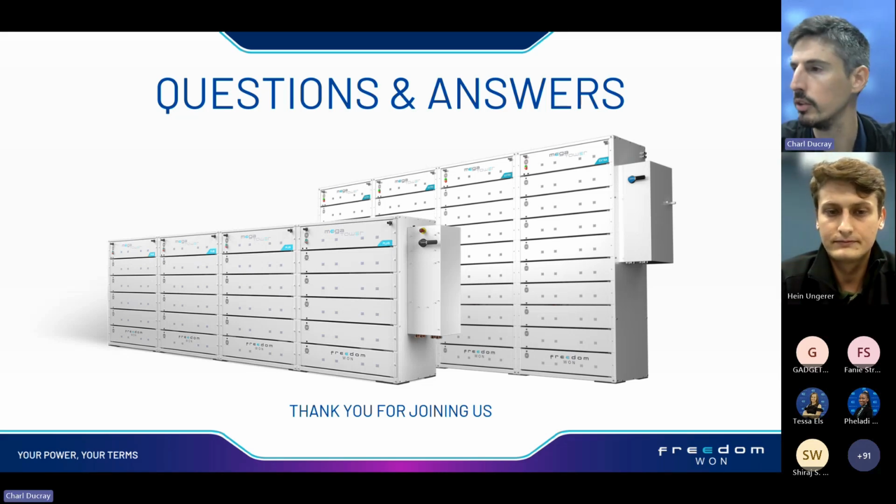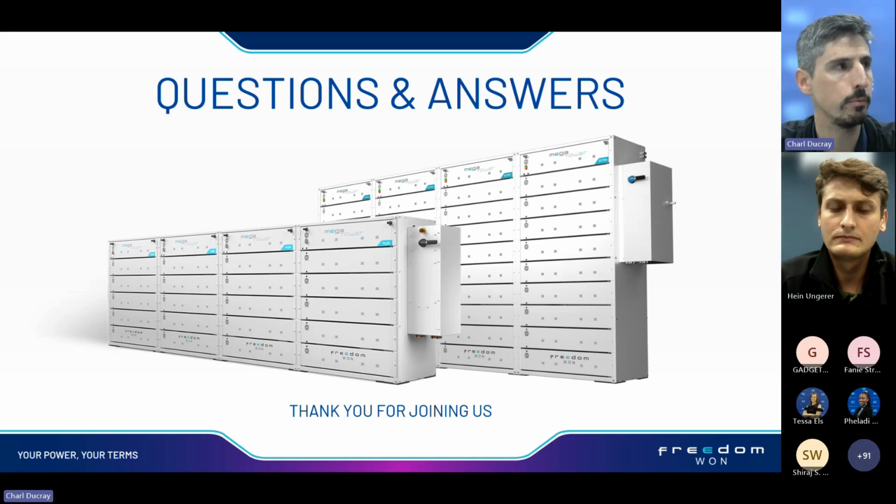Awesome. Thank you for that, Han. Then we've just got a question here about the C rating. So what is the rated or constant C rating of the modules? If I'm not mistaken, I think it's 0.7 C. Yeah, so for warranty, I think it's a continuous 0.5 C discharge and a 0.25 C charge for warranty retention, but it is designed for, I think, up to 0.8 C, but I'll just need to check the spec sheet to make sure.